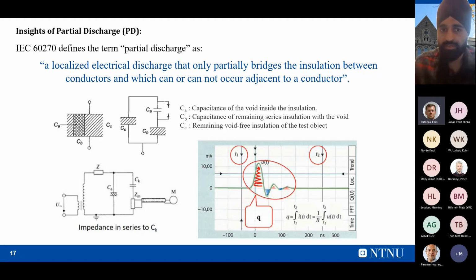So that void is represented by Ca, and the material which is present in series with this void will be represented by CB. The remaining part of the test object, which does not have any kind of void, will be represented by CC. So CC is the remaining void-free insulation of the test object, CB is the capacitance of the remaining series insulation with the void, and Ca is the capacitance of the void inside the insulation.